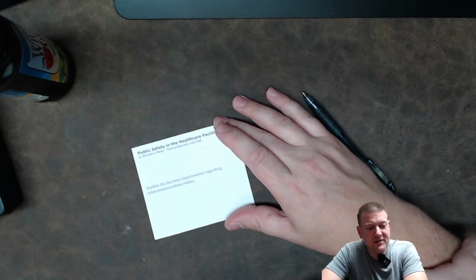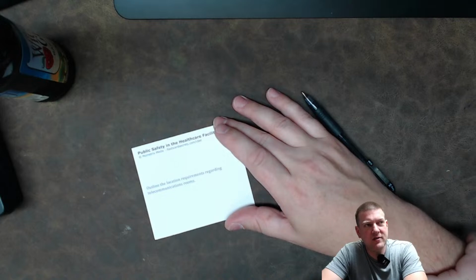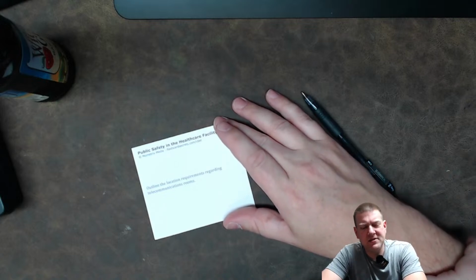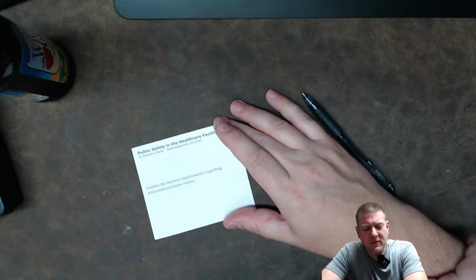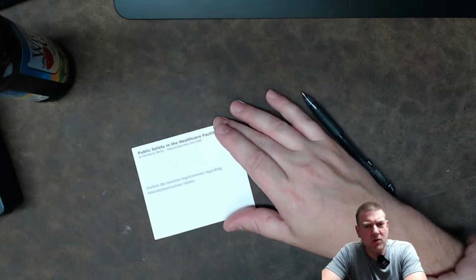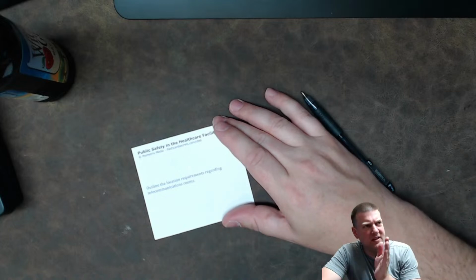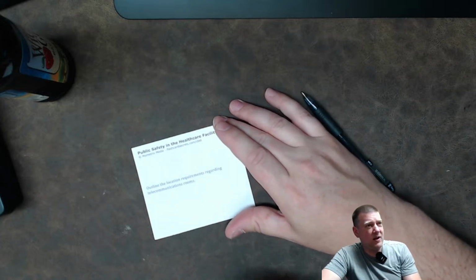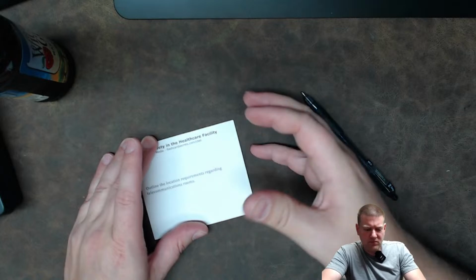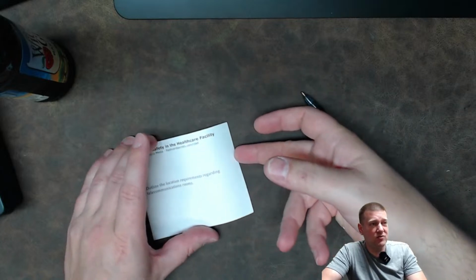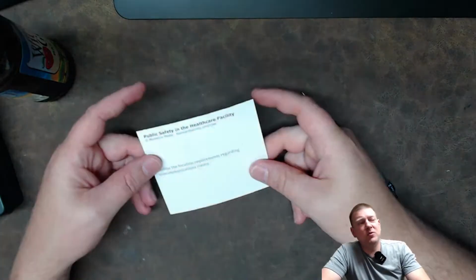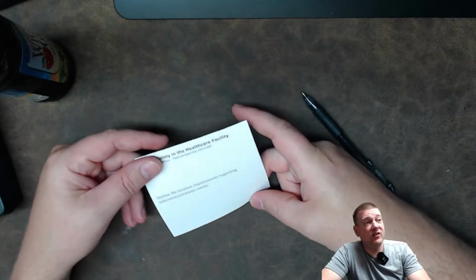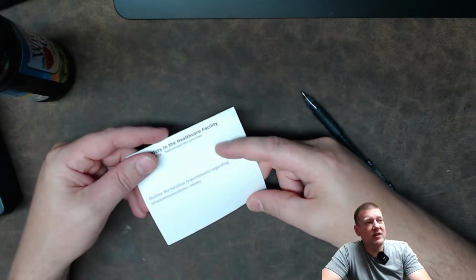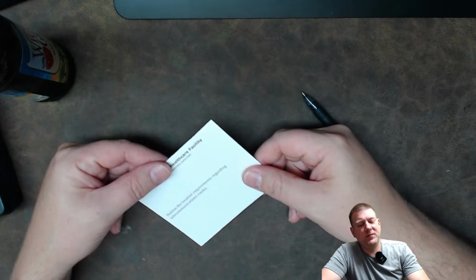I think it said that your longest comm line can be 90 meters. And they have to be accessible to the inside of the facility, not to the outside. Also, telecommunications rooms are only supposed to contain telecommunications equipment, it's not a storage area. Let's see what they say.